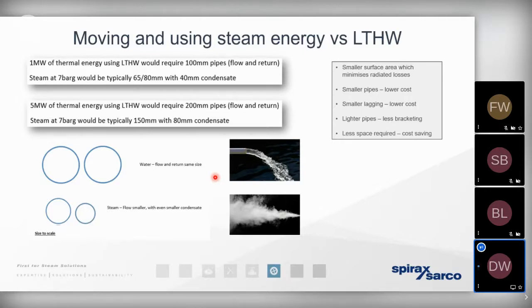The other thing is steam's a gas, it's compressible. So of course we can distribute the heat energy in the steam in a much smaller pipe diameter when compared to a low temperature hot water system. We also know with a liquid based system, we've got a single phase liquid going out and a single phase liquid coming back from the process. But when we compare that with a steam based system, we know steam gives up its heat energy by condensing. That phase change from a gas to a liquid condensate means we've got the steam going out in a very small infrastructure, but we've got the condensate coming back in an even smaller infrastructure.